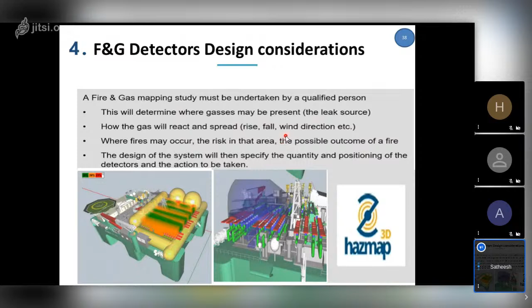So this is what I explained. This piece of gas detectors cannot do the complete job. So we need a fire and gas system or a control system. It can be PLC, it can be DCS, it can be ESD. The reason for this dedicated fire and gas system is that, since the discipline itself is a safety issue, we will not mix the fire and gas signal with the normal process signals or factory automation signals. So these panels are called the fire and gas system or controller.